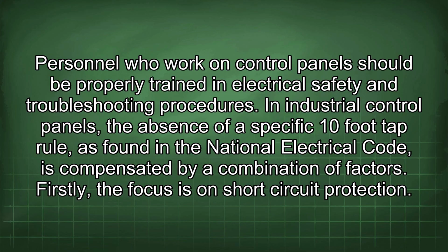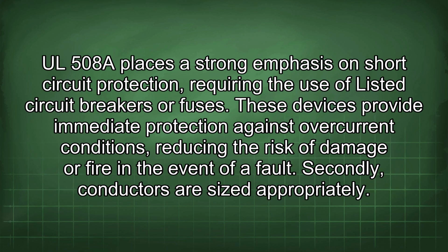In industrial control panels, the absence of a specific 10-foot tap rule, as found in the National Electrical Code, is compensated by a combination of factors. Firstly, the focus is on short-circuit protection. UL 508A places a strong emphasis on short-circuit protection, requiring the use of listed circuit breakers or fuses. These devices provide immediate protection against overcurrent conditions, reducing the risk of damage or fire in the event of a fault. Secondly, conductors are sized appropriately.